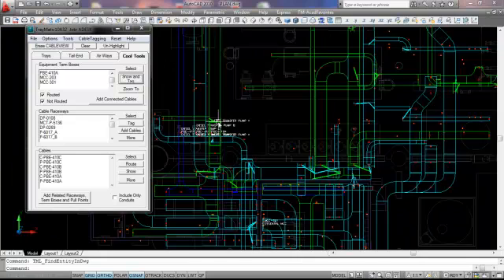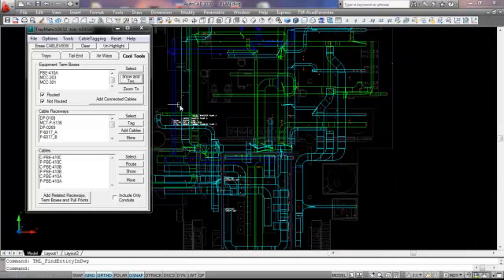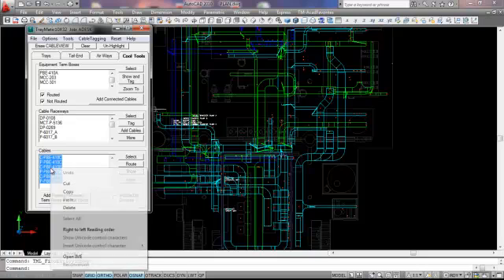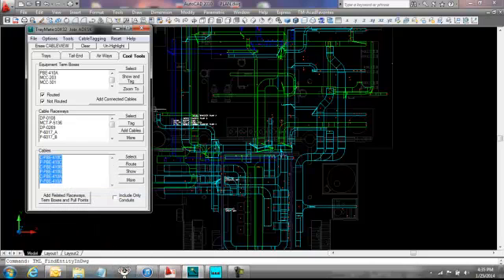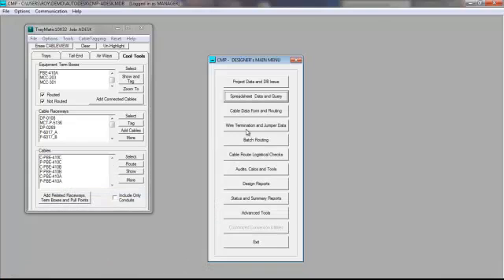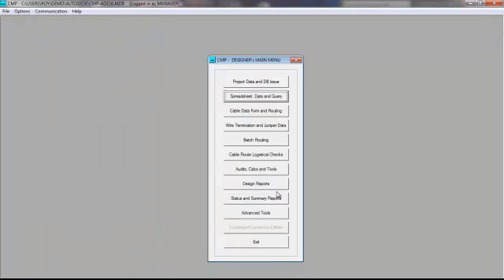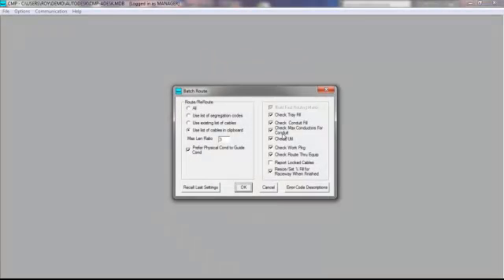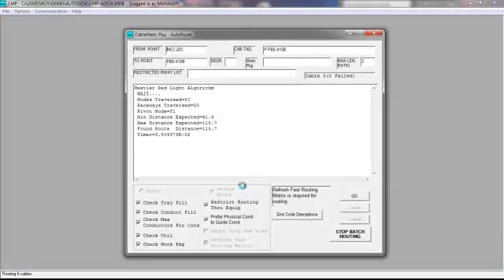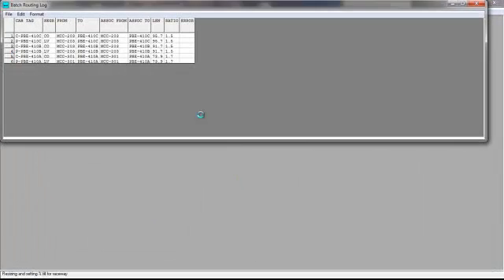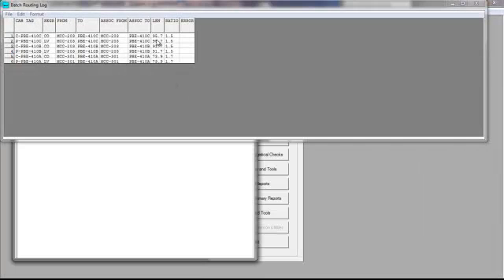Now that that's done, I'll take this list of cables and go over to CableMatic and we're going to batch route. I'm going to batch route the cables that are in my clipboard. This is all the default settings. I'm just going to leave those as they are for right now. It went ahead and routed those six cables and I'm coming up with cable routes somewhere between 73 and 95 feet on those particular runs.